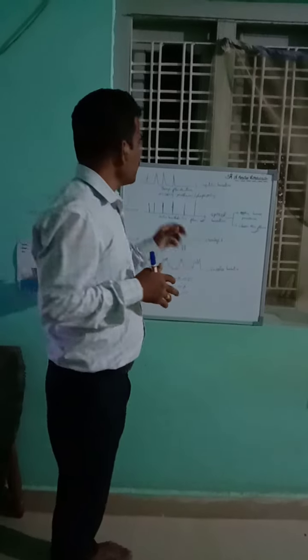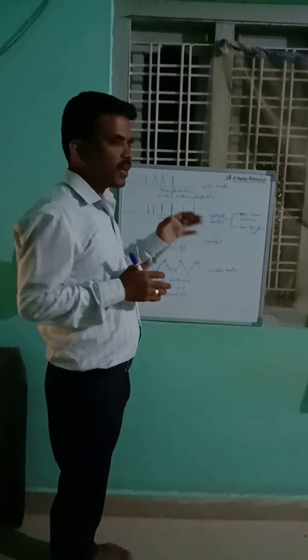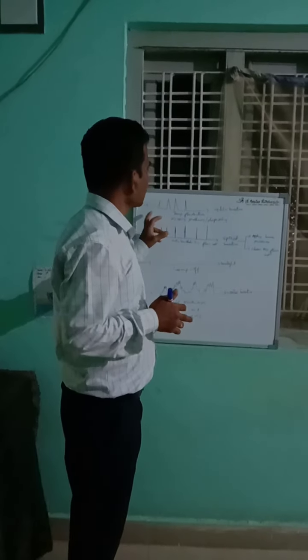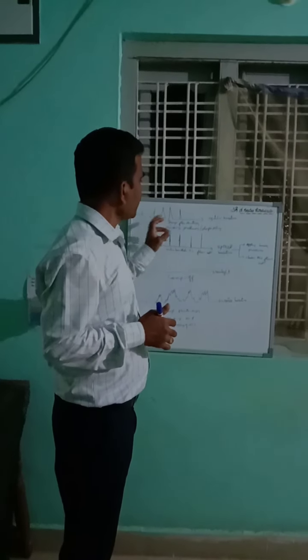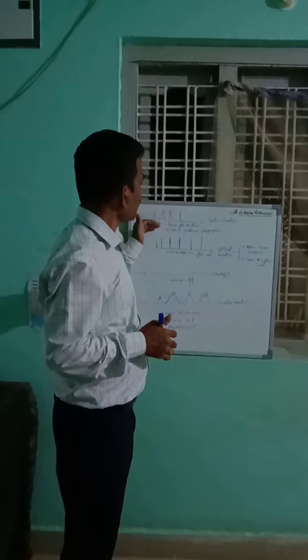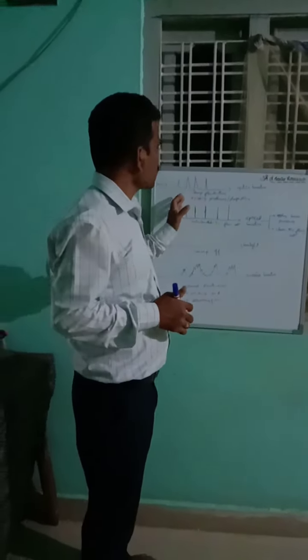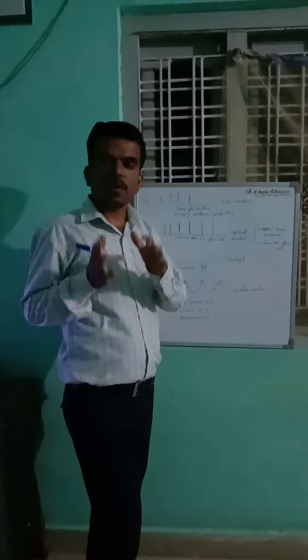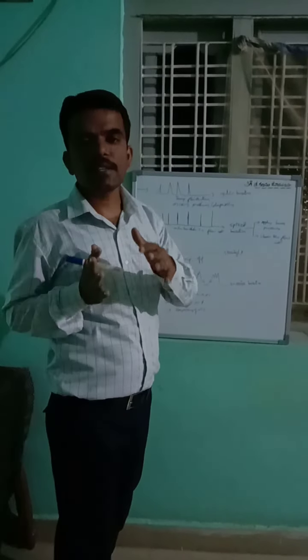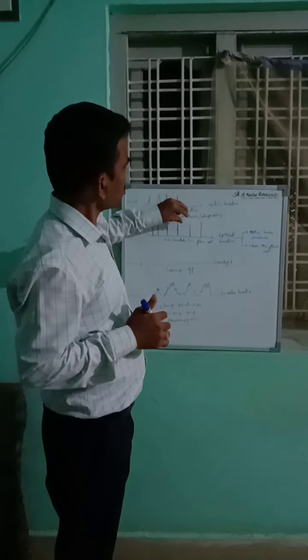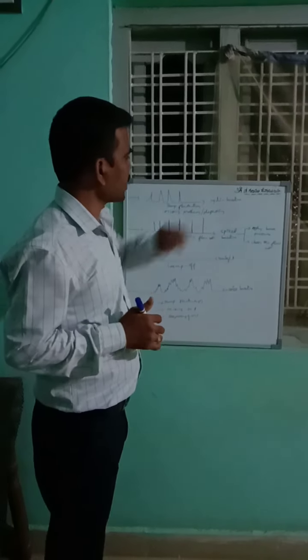When you have a temperature problem, like your column temperature or environment temperature, you get a baseline like this. To mitigate it, you have to first arrest the temperature fluctuation, and also mix the mobile phase properly and degas the mobile phase properly. In this way, we will reduce the cyclic baseline.